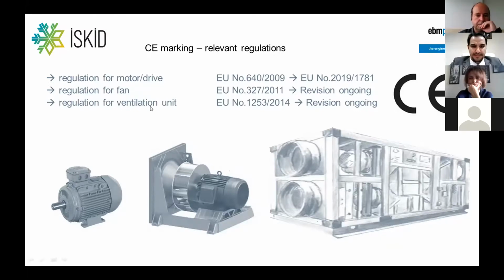And we have the regulation for ventilation units, which you are aware of, I'm sure. There's also a revision ongoing. So it can happen that the manufacturer of the air handling unit has to take care of regulation for the motors, for the fan, and for the unit itself. At least the documentation has to be made available.